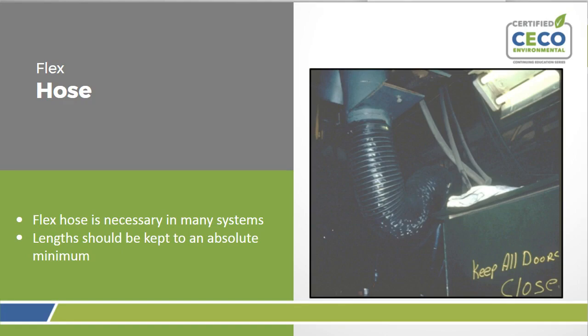Flex hose, as you see in this photograph, again, flex hose is necessary in many systems, but you want to keep the length of that to an absolute minimum. What you see here in this photo, this thing has actually formed a P-trap in the duct. There's the equivalent of 4 90-degree elbows, plus flex hose, the inexpensive kind, is rippled on the inside wall, so the loss factor for the friction is much higher, like 3 times higher than it is for typical round duct. So again, you want to keep that to a minimum amount. The reason hoods sometimes move, but again, you could have had that duct higher so that when the hood did move, the flex hose would stay in more of a straight configuration.